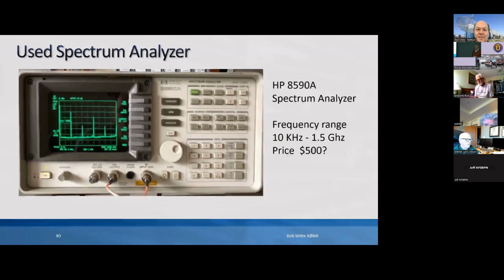Yeah, Jeff. Another thing about used gear like this is you don't know how well calibrated it is. And what is it going to cost you to get it calibrated, depending on what you're going to use it for? So you have to take that into consideration. If it's going to cost you $1,000 or something to send it out to have it calibrated, that's a good point. It could easily cost you that much to get its cal. But good calibration is probably better than a micro spectrum analyzer that you buy for $100. Right. And I think that's where you differentiate between hobbyist stuff versus equipment that you are using professionally that is supposed to have a guaranteed measurement result, then you need to be thinking calibration. And so that becomes kind of like a maintenance cost, right? You have to calibrate it every once in a while.